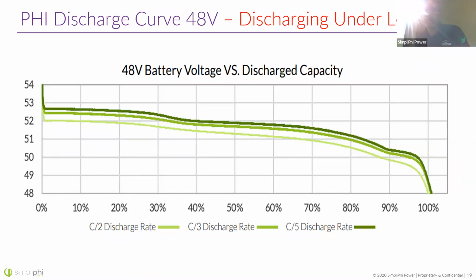I'm only giving you this characteristic for a 48-volt battery. Cut everything in half, and it's the same looking graph for a 24-volt battery. It's a little better for 24-volt batteries because they have more batteries in parallel, so you don't see quite as much of a drop due to less internal resistance. The heavier the load, the more below the resting voltage you will be. This is what makes it hard to determine the state of charge of your battery bank while it's loaded.